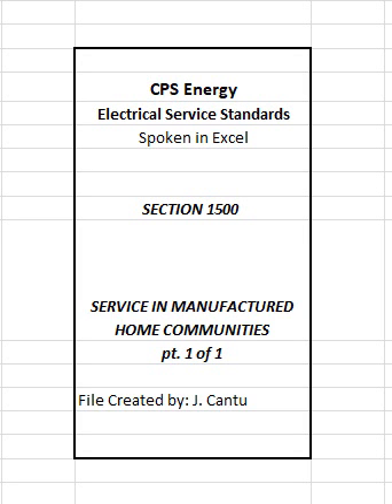Meter pedestals shall be mounted on or concrete embedded in a minimum 18-inch diameter by 20-inch depth concrete base. Meter pedestals shall meet all specifications and be approved by CPS Energy prior to installation. Refer to Figure 1501. Customer shall install the pedestal as specified in Section 1800 and shown in Figure 1501. Customer must notify CPS Energy in advance as to the type of pedestal to be used. Note: only 1 meter per pedestal shall be permitted by CPS Energy.